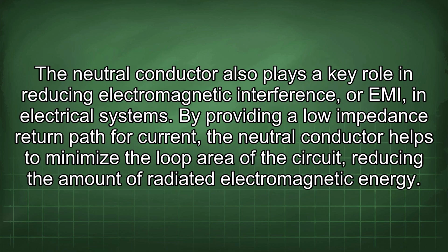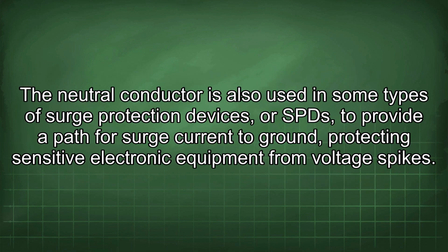The neutral conductor also plays a key role in reducing electromagnetic interference, or EMI, in electrical systems. By providing a low impedance return path for current, the neutral conductor helps to minimize the loop area of the circuit, reducing the amount of radiated electromagnetic energy. The neutral conductor is also used in some types of surge protection devices, or SPDs, to provide a path for surge current to ground, protecting sensitive electronic equipment from voltage spikes.